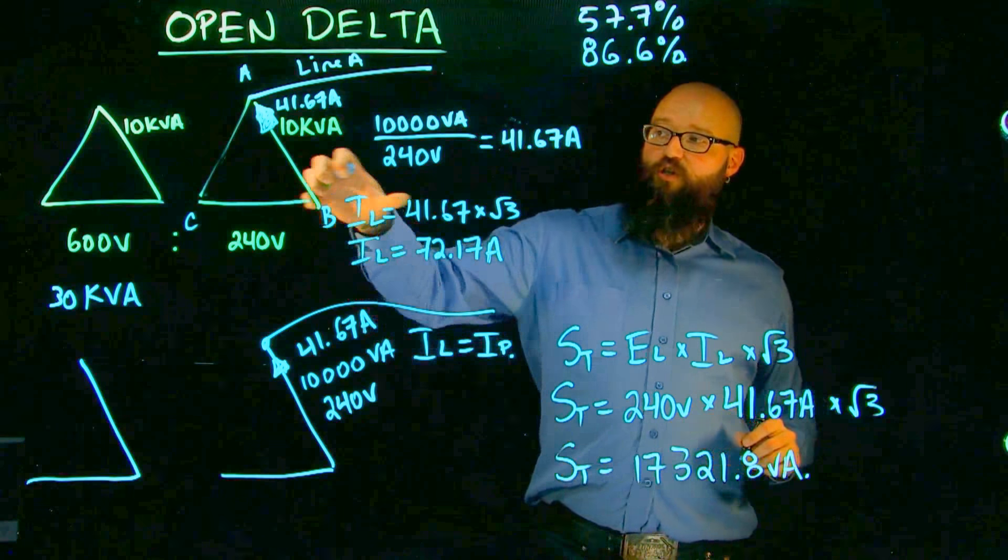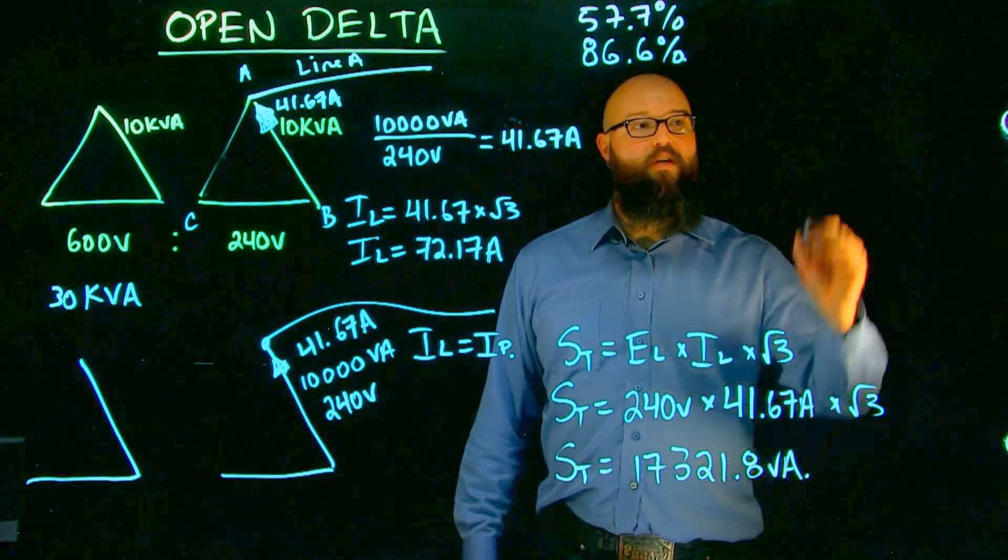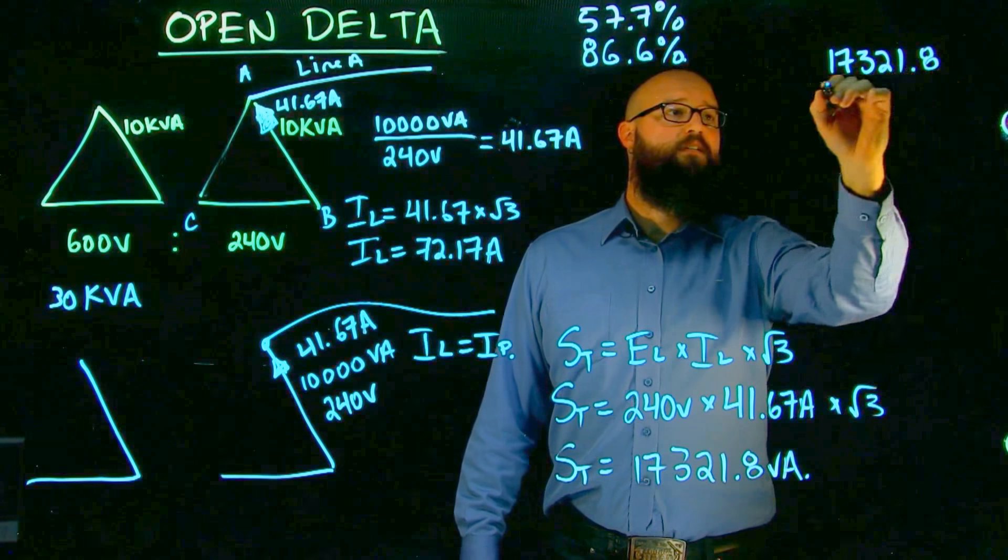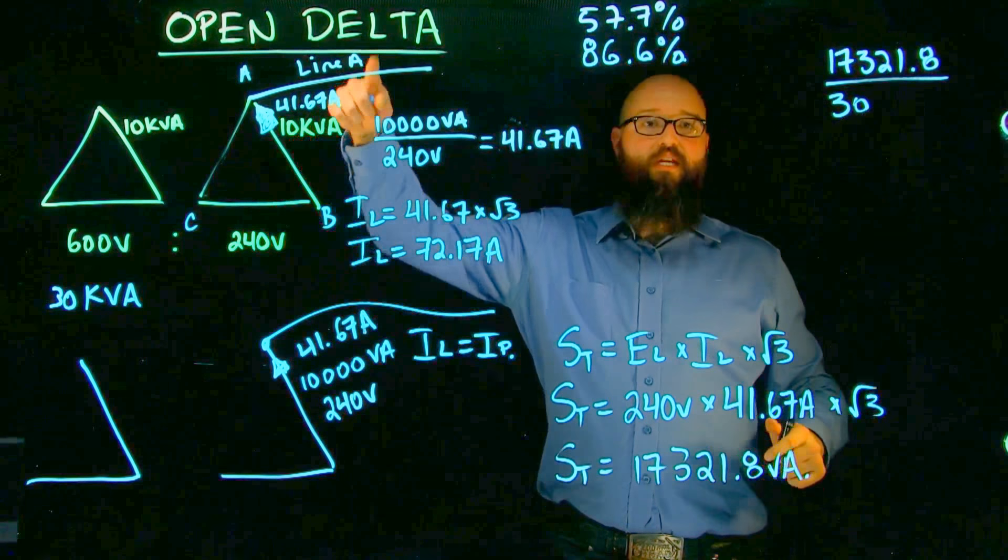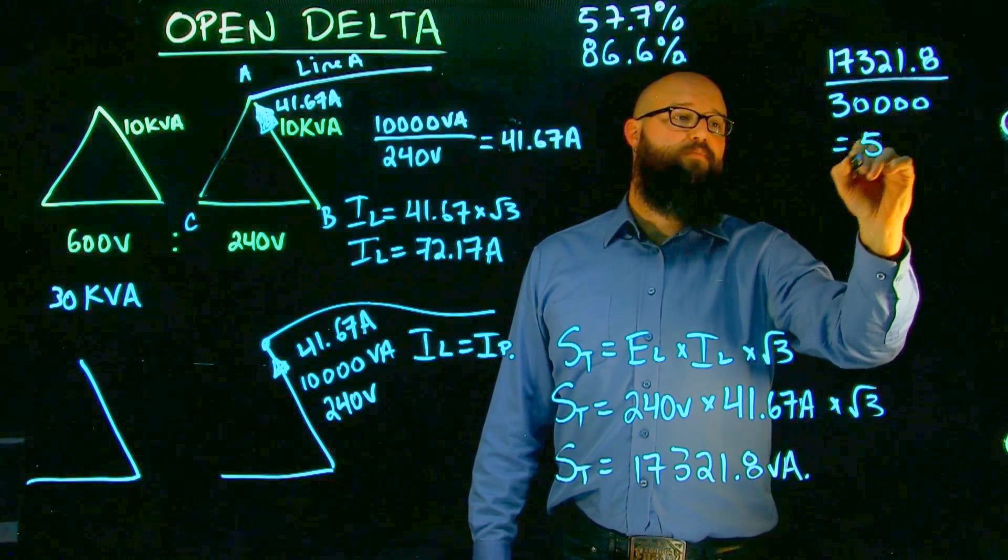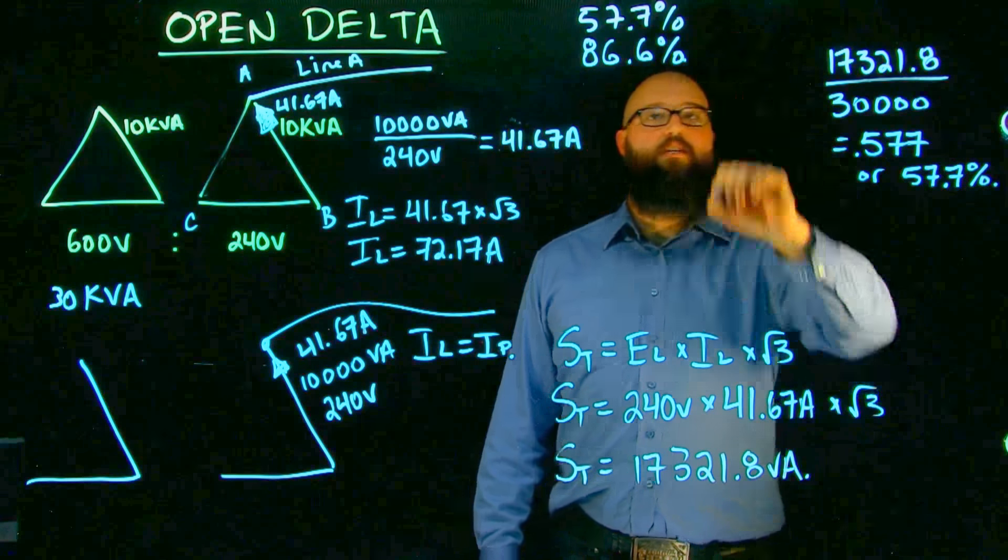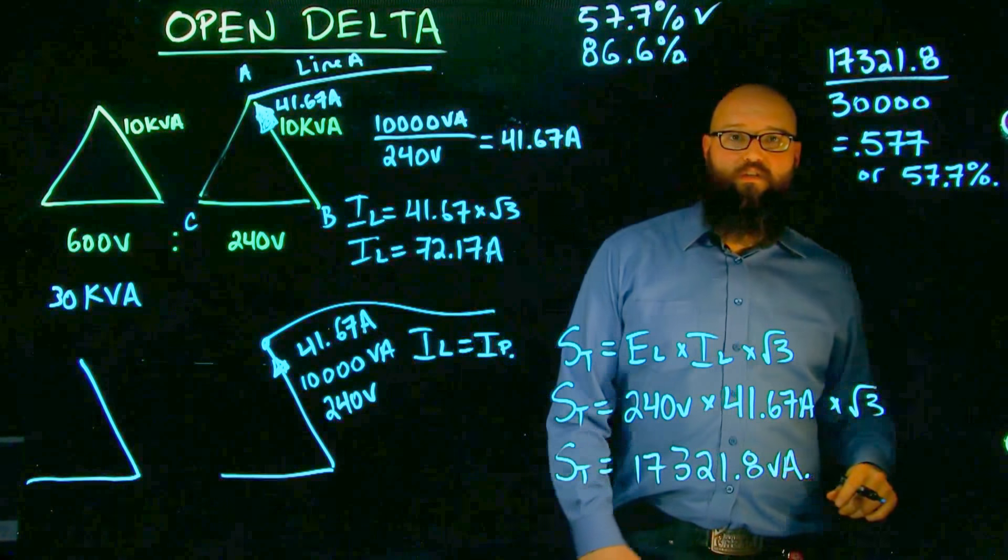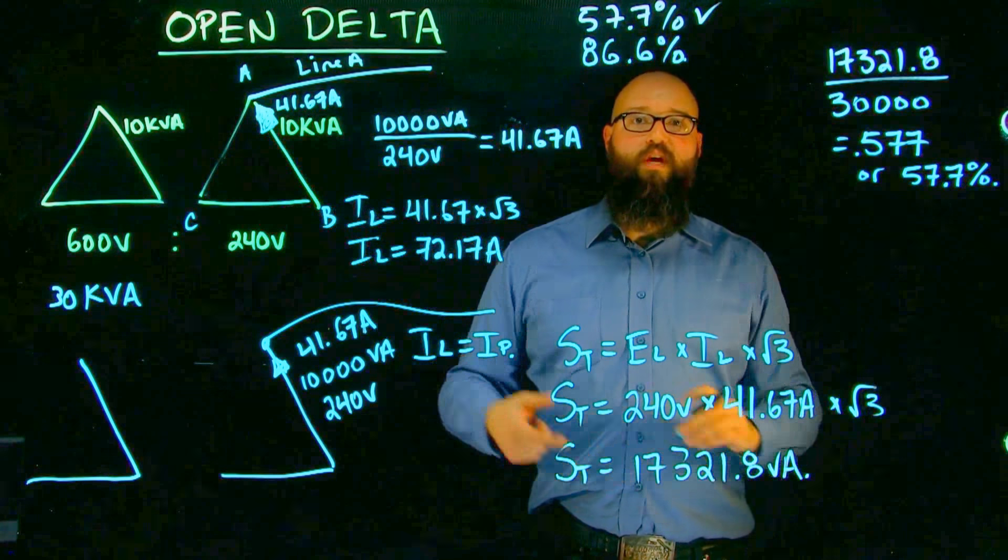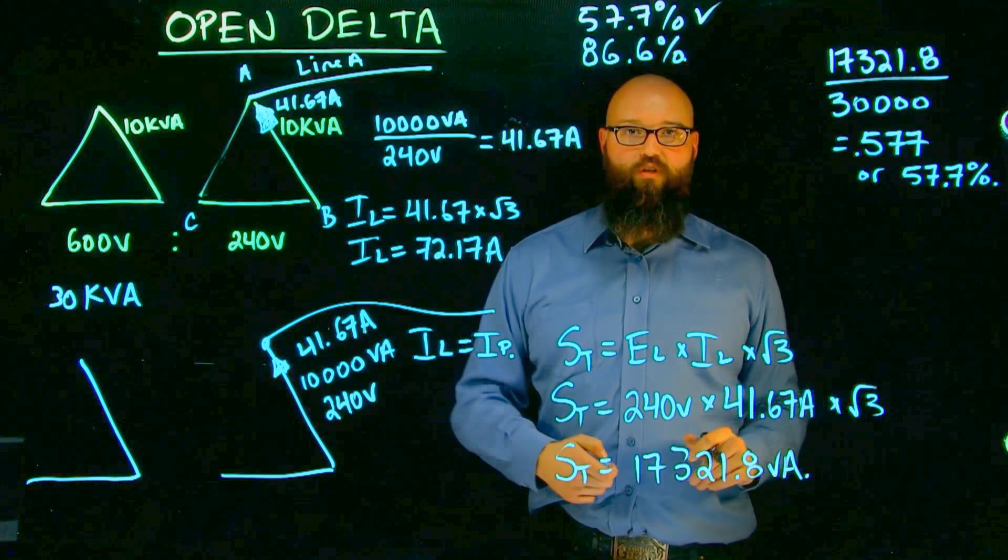Okay, now let's look at those numbers. Originally, these three phases, this was a 30,000 VA output. And if we look at this number, 17,321.8 divided by our original three 10 kVA transformers of 30,000, we end up at 0.577 or 57.7%. There's our first percentage. Okay, that's when we compare it to those three coils, what they would have originally put out compared to what they're putting out now is reduced to 57.7% of what it originally was.